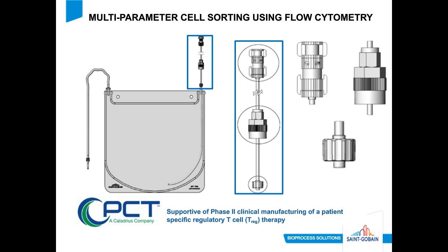So this goes back to understanding material selection and looking at the criteria that the product has to perform in. And so this is where tubing had to be identified that could hold up to the pressures of the application. And that story remains true with the connections that we had to make to the flow cytometer, looking at pretty sophisticated connections, including metallic components, in order to make sure that it could hold the vacuum under the application of the flow cytometer.